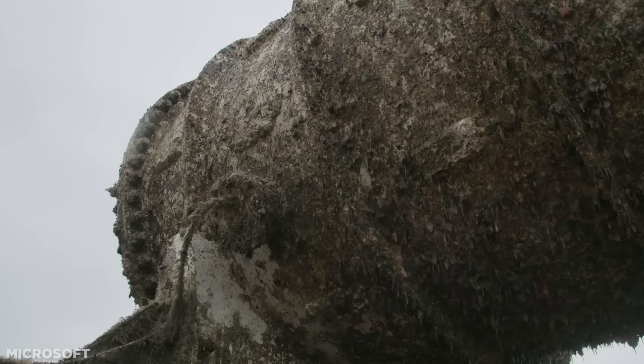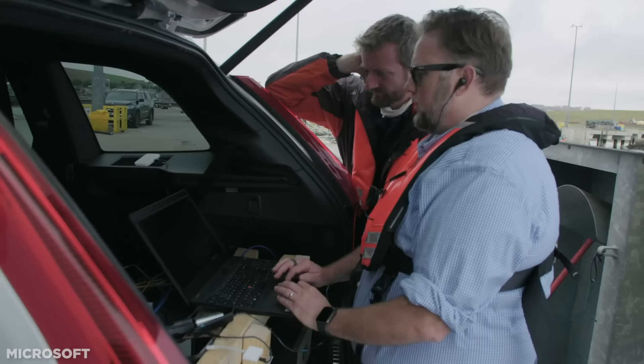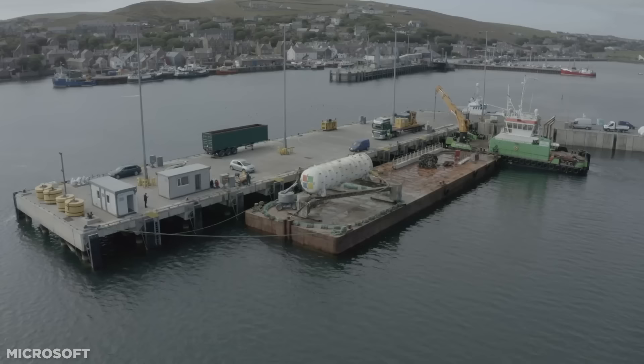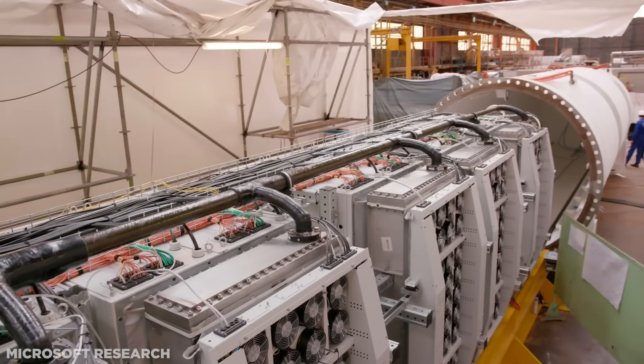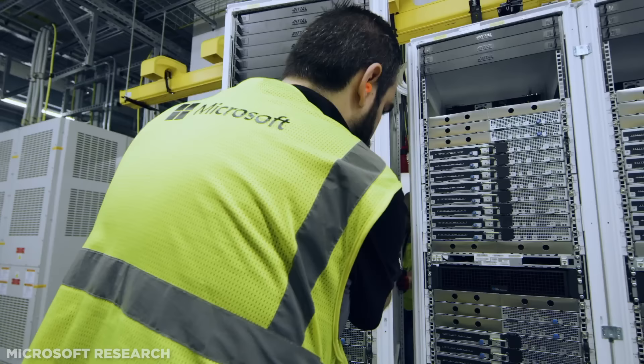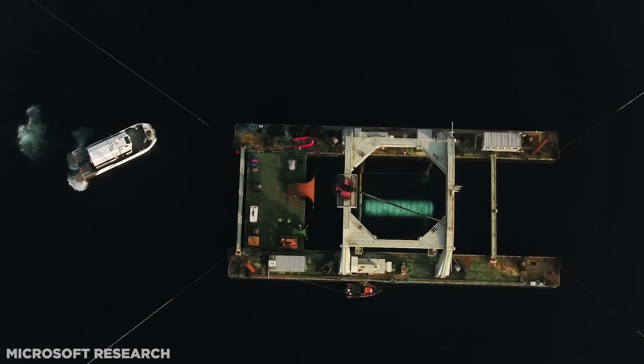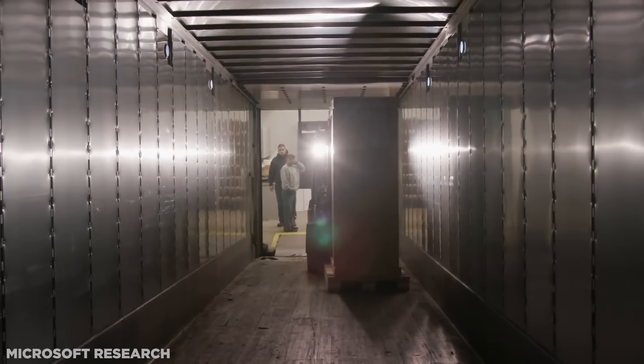So, the Northern Isles spent just over two years under the sea, gathering data along its journey. Another full day of retrieval pulled up the same white container, with a thin covering of algae, barnacles and sea anemones. A quick wash resulted in surprisingly clean bodywork emerging from underneath. From this one experiment, the various teams of engineers and researchers at Microsoft have deduced that sinking a data centre like this is eight times more reliable than housing computers in land-based warehouses, although why, they're not sure. Despite a handful of failed servers which were taken offline, no maintenance was carried out for the duration of the testing stage. They believe that being filled with dry nitrogen — a substance that is less corrosive than the oxygen that forms part of the air on land — may have something to do with its extraordinary success.